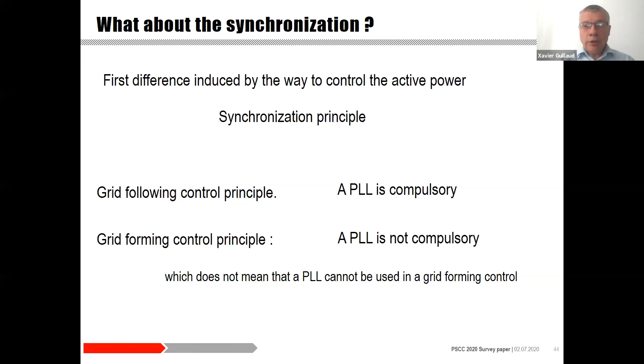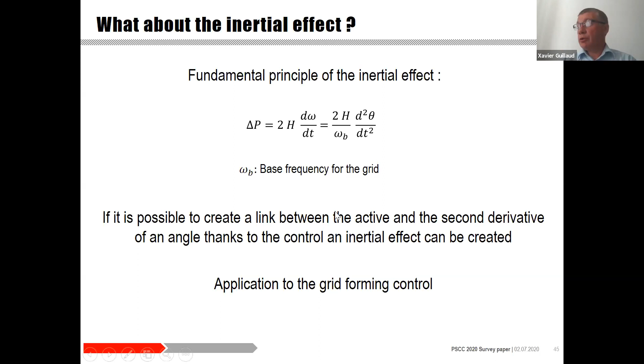Let's see now the influence of the choice of the active power controller on the way to generate an inertial response. The fundamental principle of the inertial effect is a link between a power variation and the derivative of speed, meaning the second derivative of the angle. If it is possible to create a link between the active power and the second derivative of the angle, thanks to the control, an inertial effect will be created. Let's apply this idea to the grid forming control.